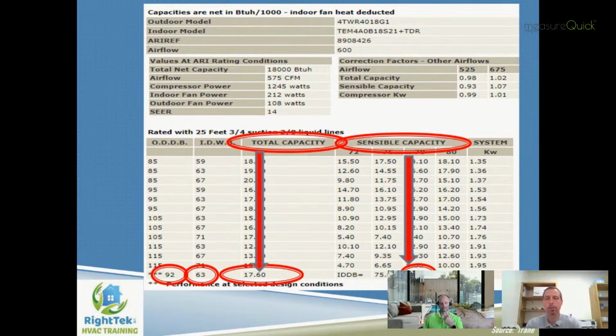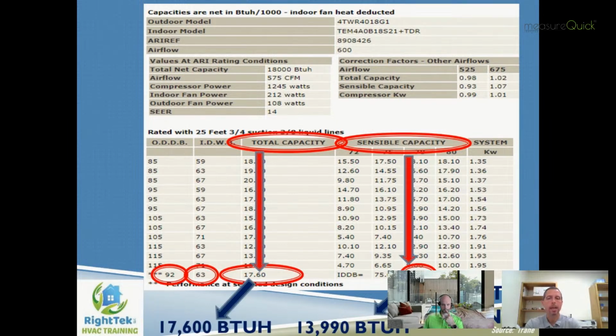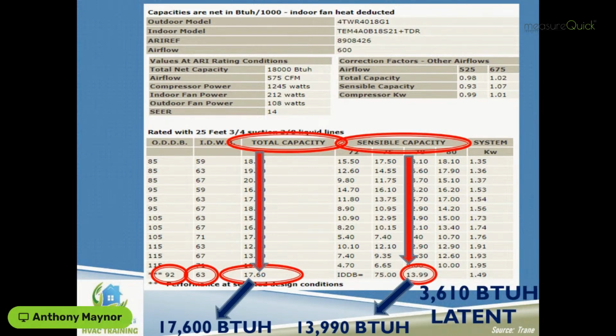So just to cut to the chase and simplify, I've gone to one major OEM. I pulled up some expanded performance data for a heat pump, looking to match up for that load that we just looked at. And if I interpolate the data that you see on the chart here to match my design conditions in the summer, which was 92, 75, and 50% RH, you can see what I've got here in terms of performance. I've got about 17,600 BTUs per hour total cooling capacity, of which 13,990 was sensible, and the remaining 3,610 was latent.